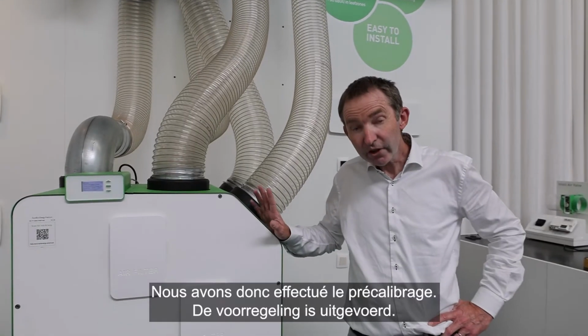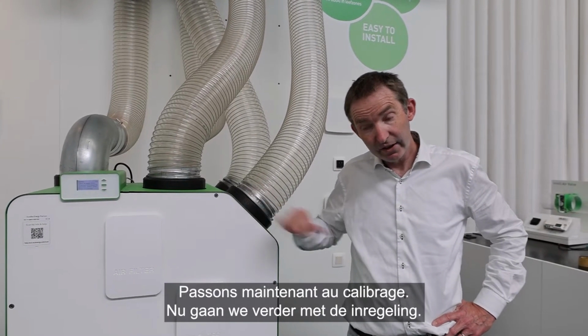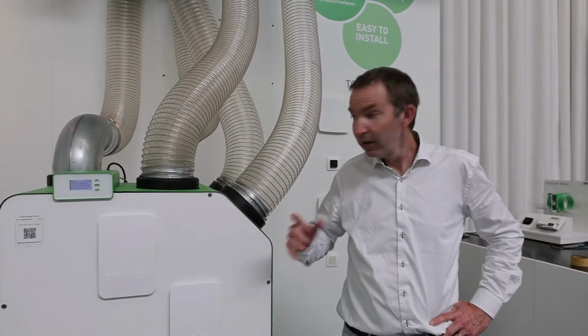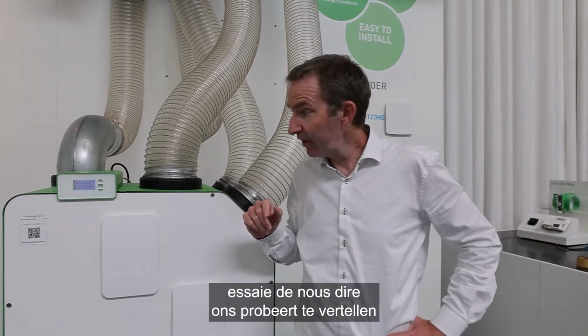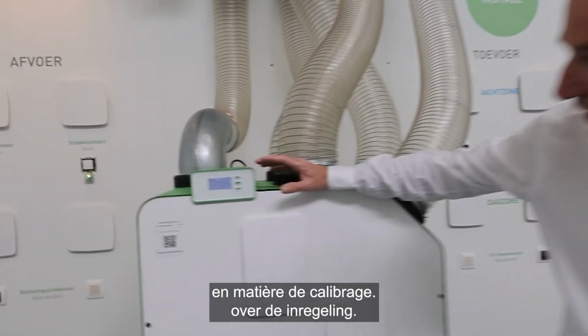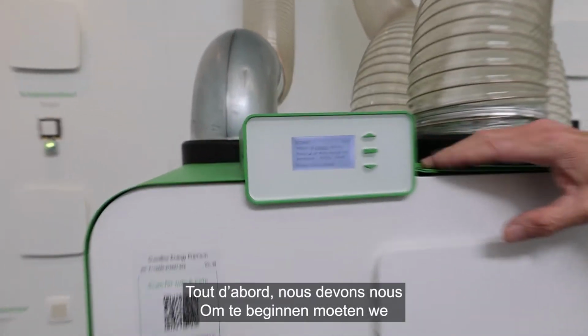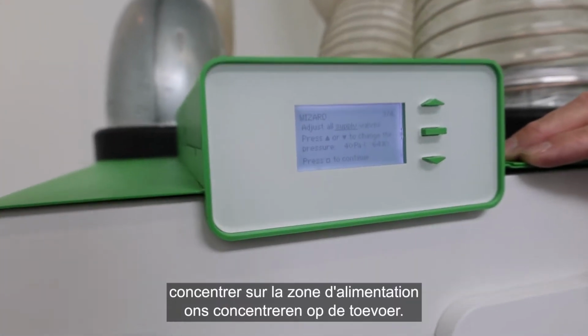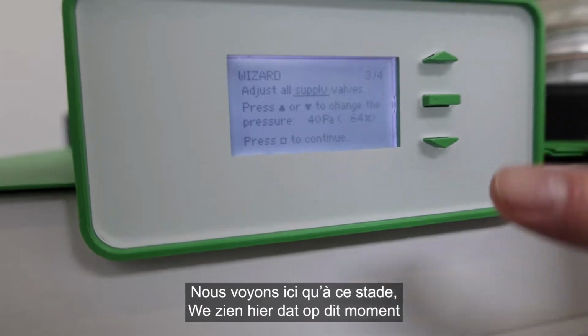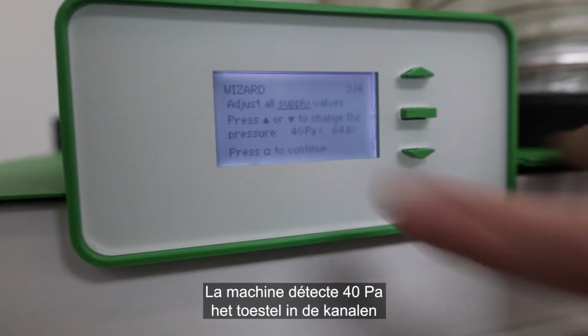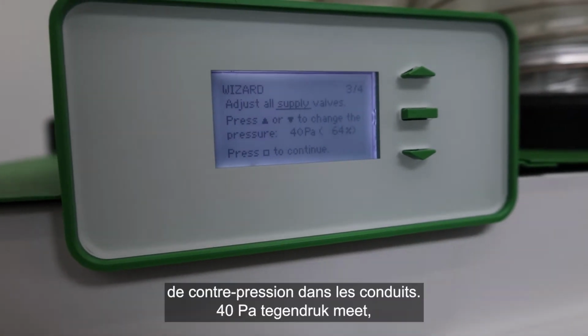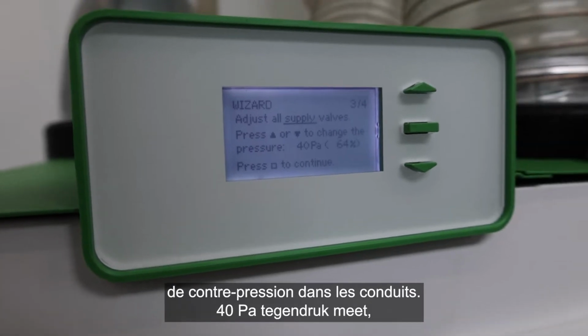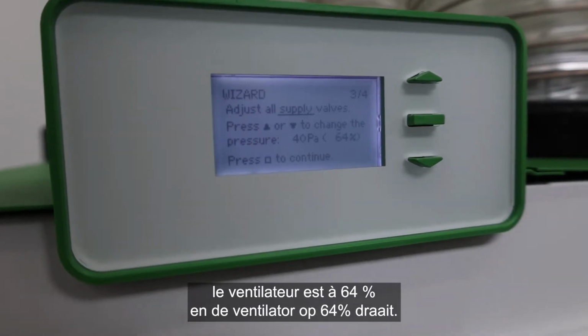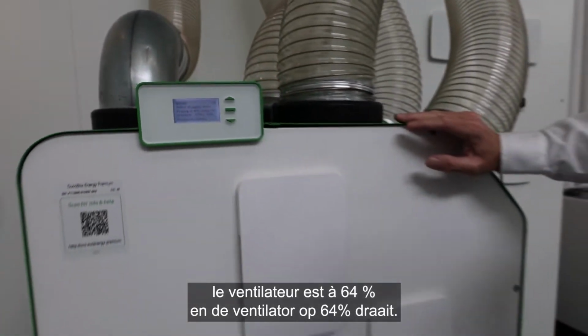Okay, so we did the pre-calibration. Let's move on now to the calibration. Let's see what the machine actually tries to tell us with respect to the calibration. So first of all, we actually need to focus on the supply area. And what we see here is, at this stage, the machine detects 40 Pascal of counter pressure in the ducts, so in the whole system, and actually the fan is at 64%.